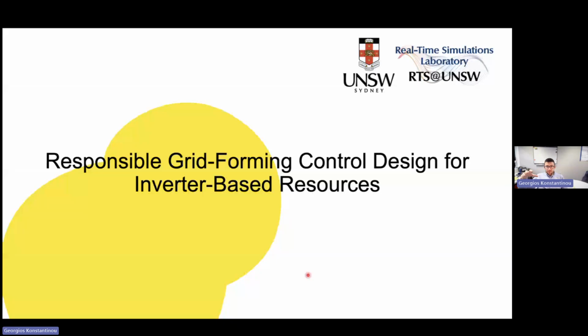So we end up with a network effectively defined by power electronics converters, meaning many functions we used to get from synchronous generators need to come, one way or another, from inverter-based resources. We need to be able to form the grid, which brings us to this discussion about grid forming converters that I'll spend the rest of this presentation on. How do we get a responsible grid forming design for our inverters in order to address all the issues introduced in the first part of this presentation?